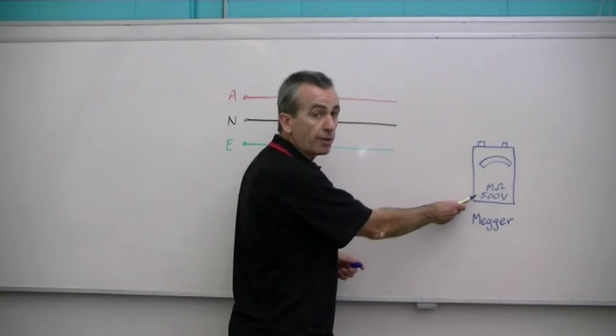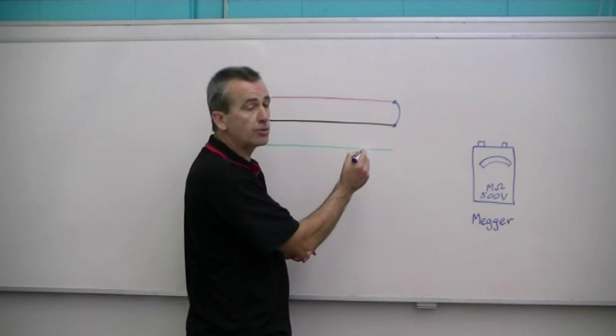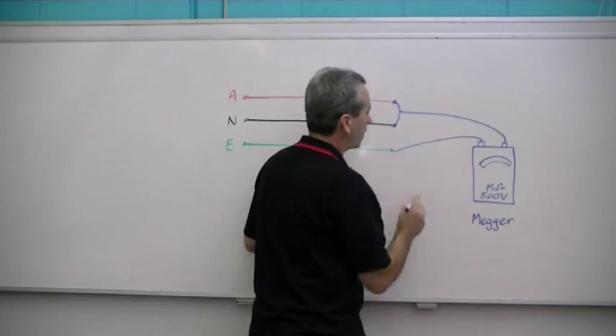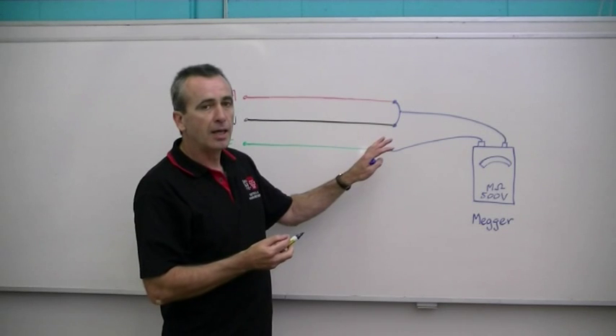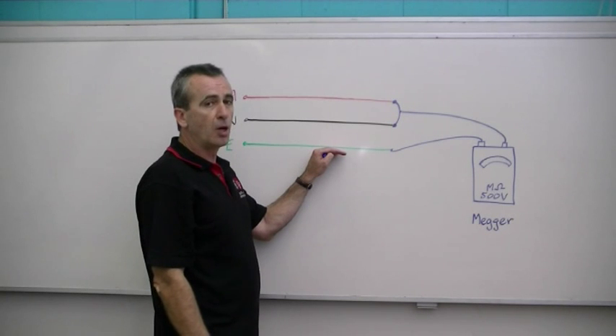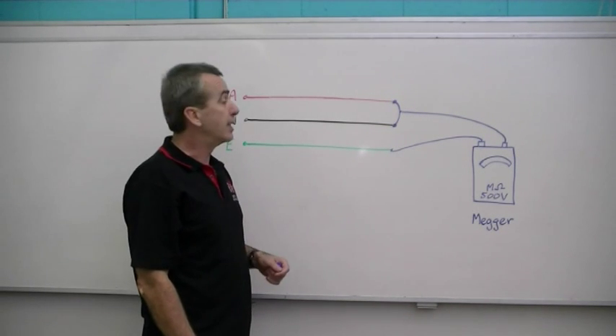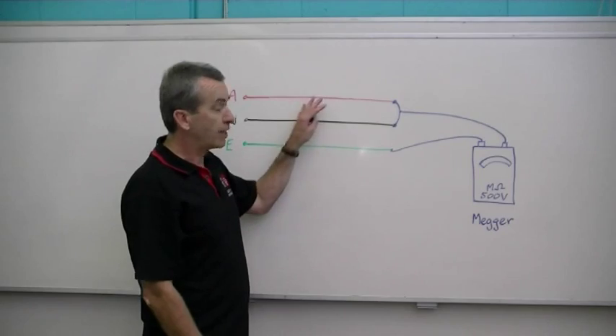To set our Megger up, we must have it on the 500 volt range. We join the live conductors together — that's the active and neutral joined together — and one lead from our meter goes to those two live conductors. The other lead goes to the earthing conductor. We're applying 500 volts between active and neutral to the earthing system, making sure they are not connected to earth. We want a very high value — the wiring standards say we need at least one mega ohm, that's one million ohms of resistance, between live conductors to earth.